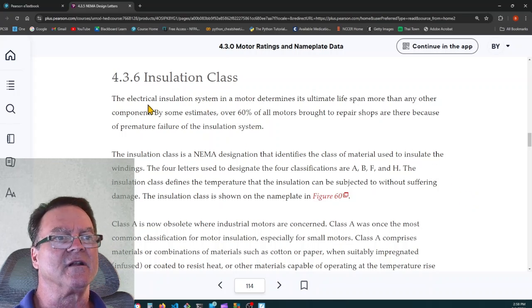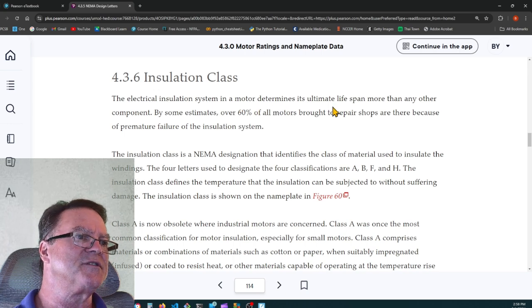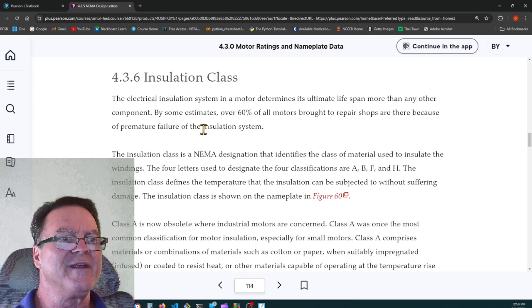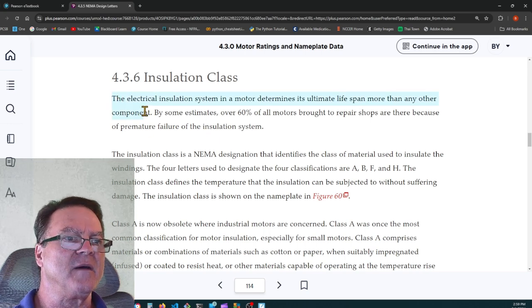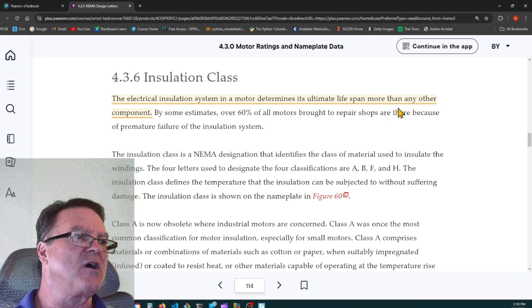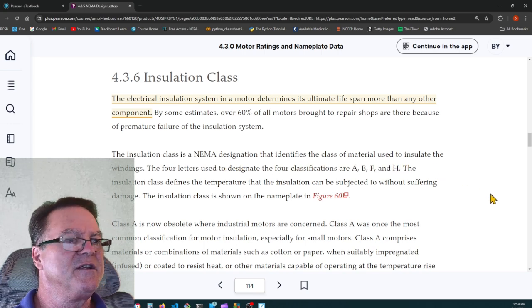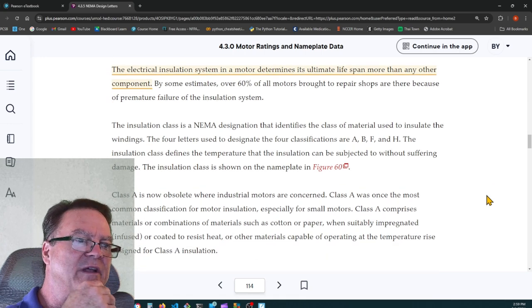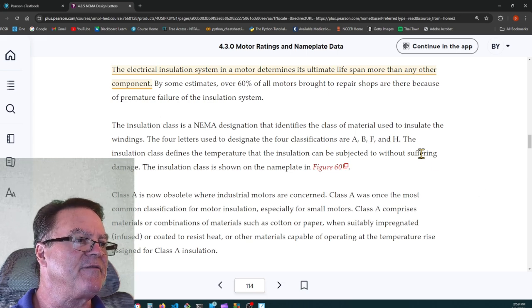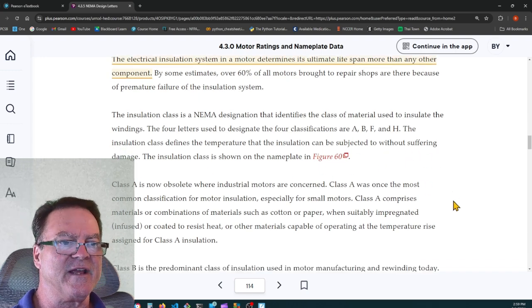Insulation class. The electrical insulation system in a motor determines its ultimate lifespan more than any other component. Man, I'm going to highlight that. That sounds important. It sounds like something they might ask you. The insulation system in a motor determines its ultimate lifespan more than any other component. By some estimates, over 60% of all motors brought to repair shops are there because of premature failure of the insulation system. The insulation class is a NEMA designation that identifies the class of material used to insulate the windings. The 4 letters used to designate the 4 classifications are A, B, F, and H. The insulation class defines the temperature that the insulation can be subjected to without suffering damage.